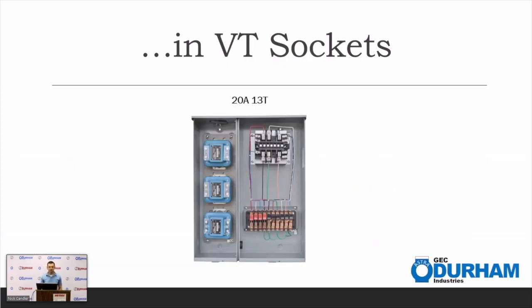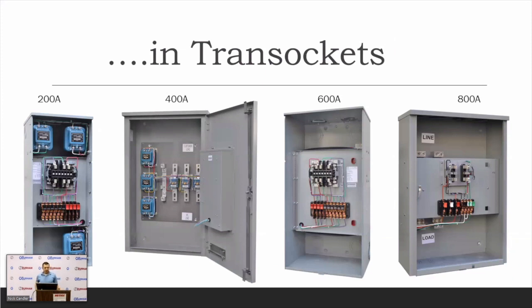VT sockets. A lot of folks don't know about these, but manufacturers make those to account for any voltage transformers. Maybe the utility will own the 20 amp socket and the voltage transformers, while the customer would own the CT enclosure, maybe in a separate location or something. But interesting, transockets are a popular option these days. As a manufacturer, we're seeing more and more utilities switch over to these. 200 amp, 400 amp, 600 amp. There's a lot of different types, styles, mountings of the 20 amp socket in the door, but these are going to include both your current transformers and a lot of times your voltage transformers as well.